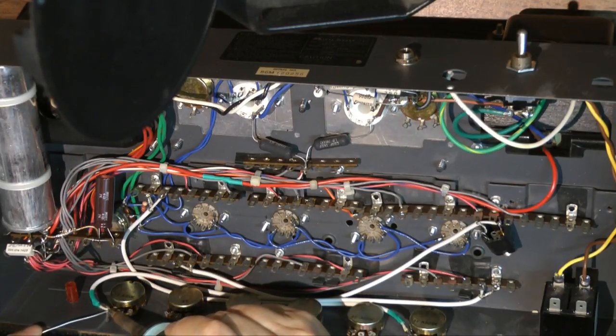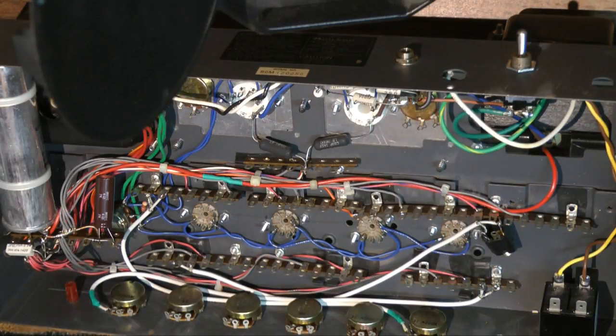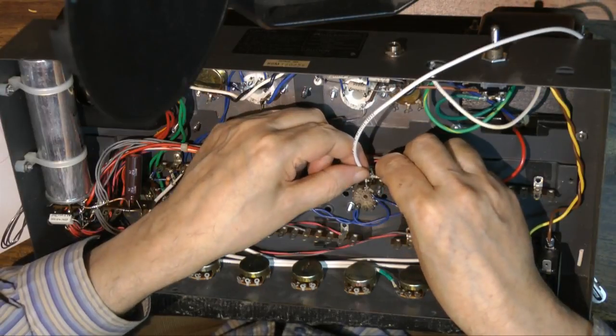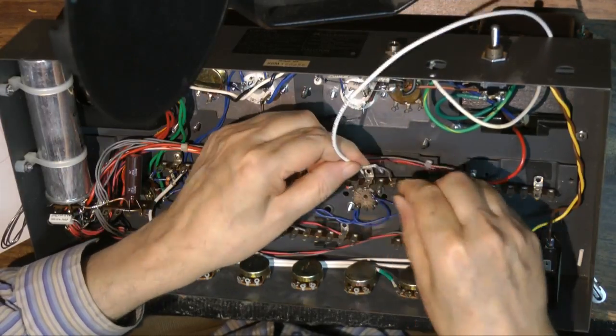Some of the cables, as you can see, the shield is only connected at one end. Sometimes if you put the shield connection at both ends, you get a ground loop.